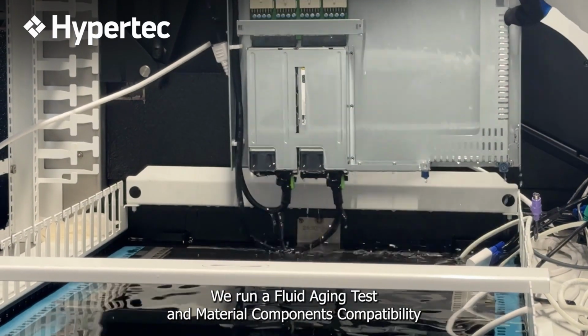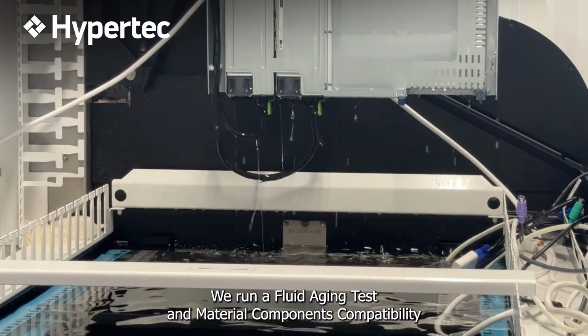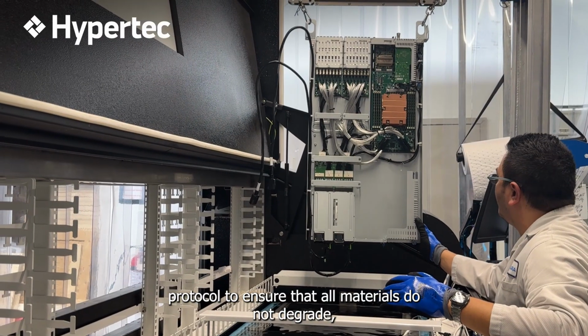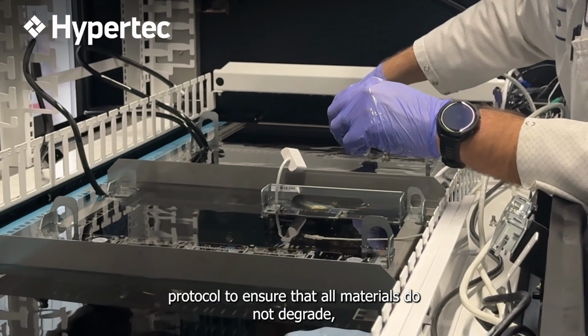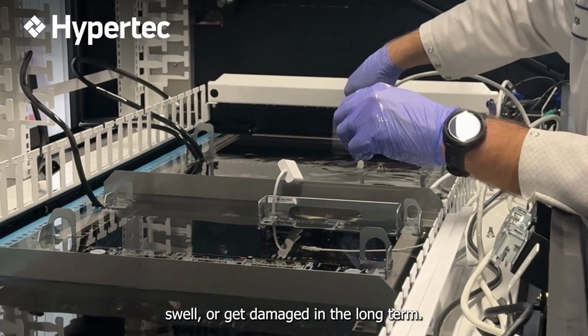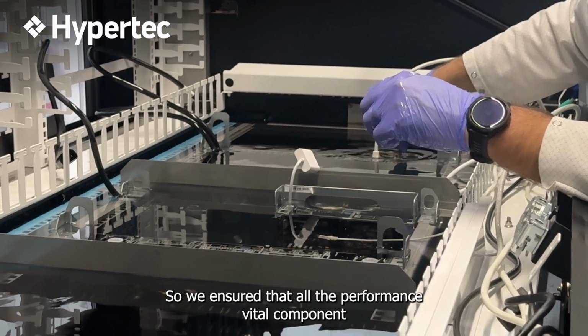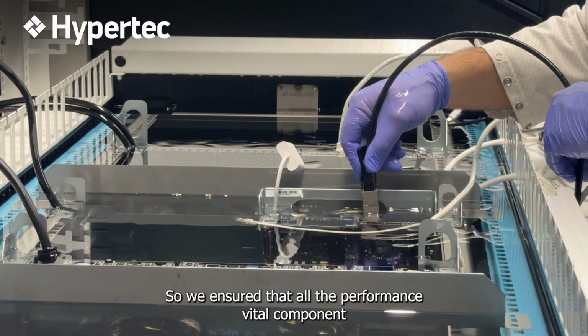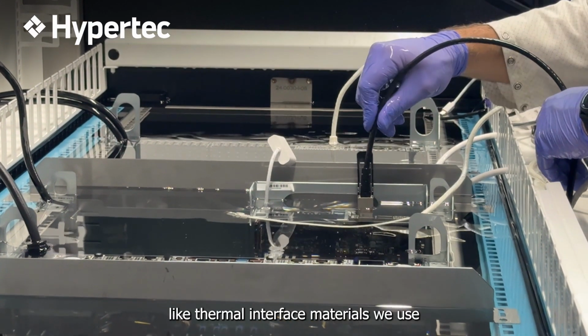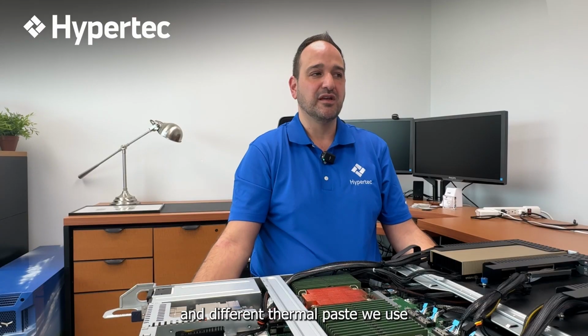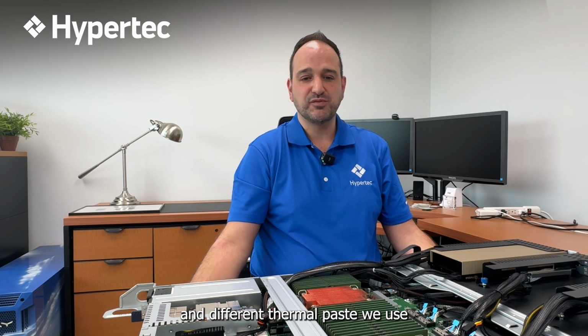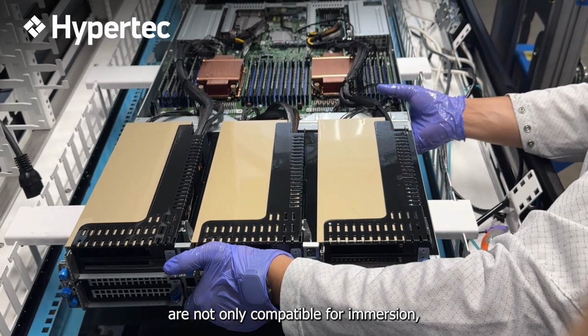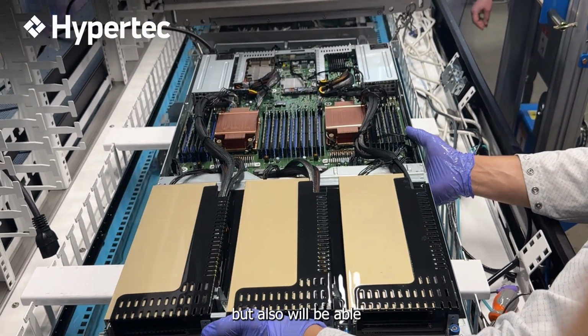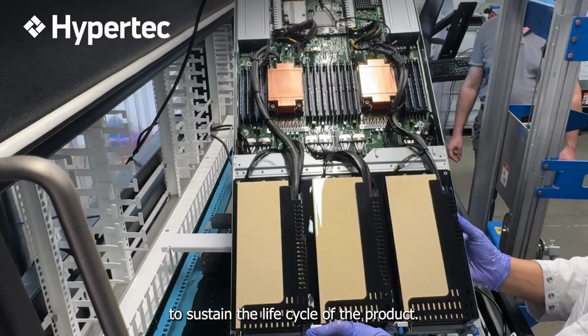We run a fluid aging test and material components compatibility protocol to ensure that all materials do not degrade, swell, or get damaged in the long term. So we ensure that all performance-vital components, like the thermal interface materials and thermal pads we use, are not only compatible for immersion, but also able to sustain the life cycle of the product.